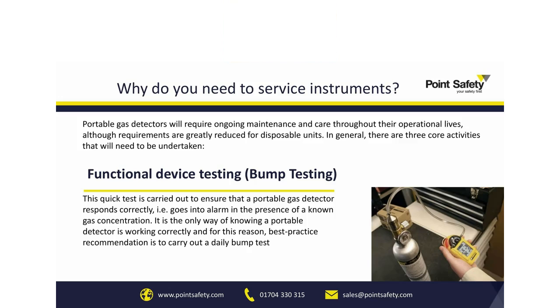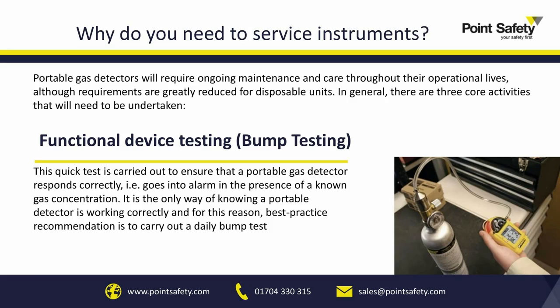In general, servicing activities revolve around 3 core areas that will need to be undertaken. Functional testing, or bump testing as it's commonly known. This is a quick test, carried out on the detector with a small amount of equipment or a docking station if available. So a bottle of test gas, a regulator and a bit of tubing, as shown in the picture, which will apply a known value of gas that will push the meter into its alarm state, and this will confirm that the meter will respond to the target gas if it does come across it in its daily activities.